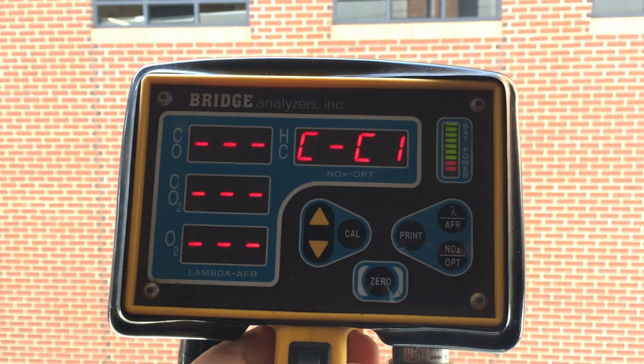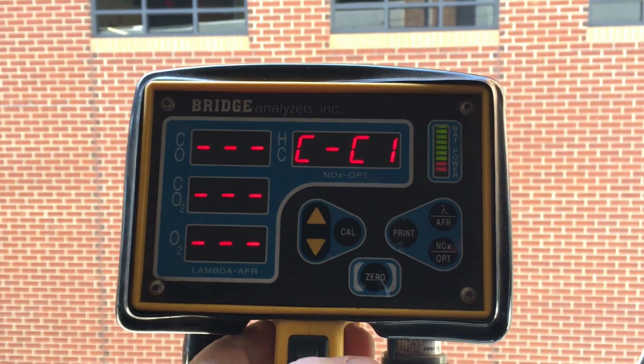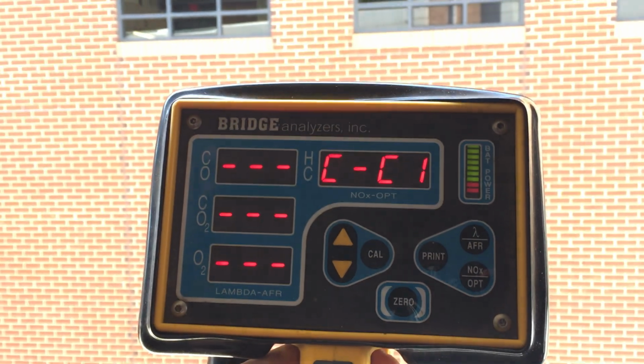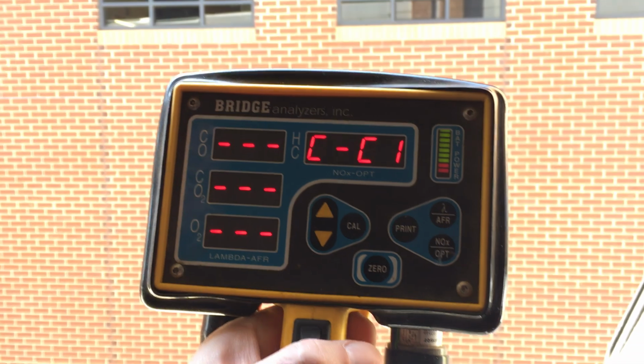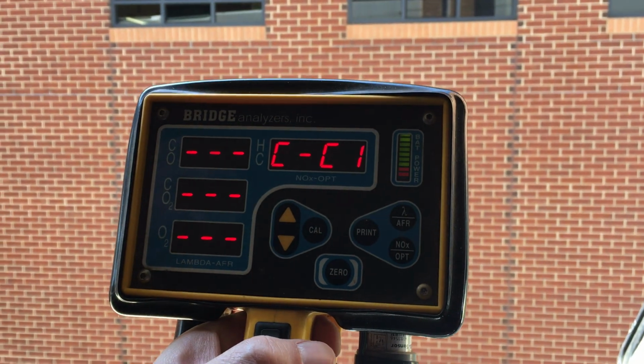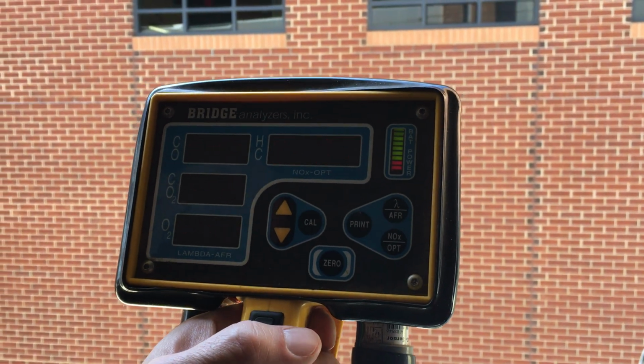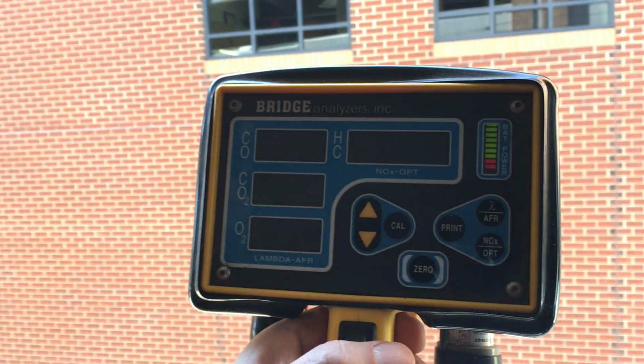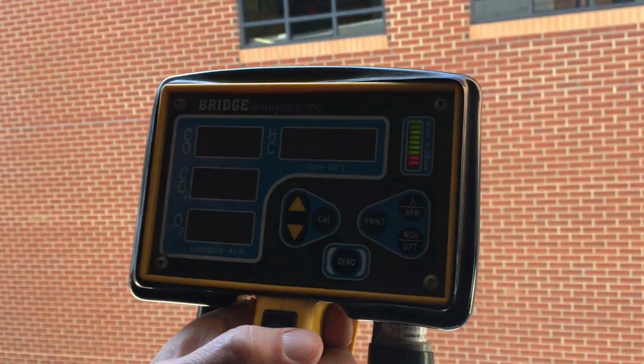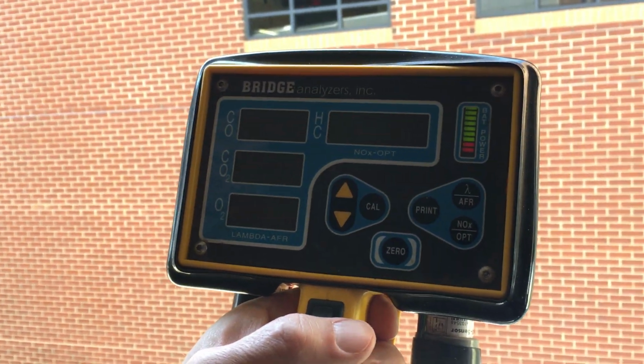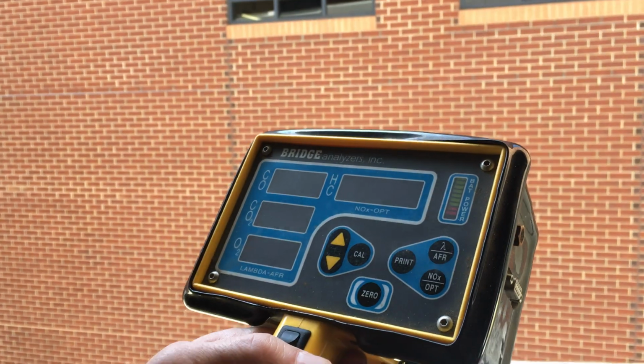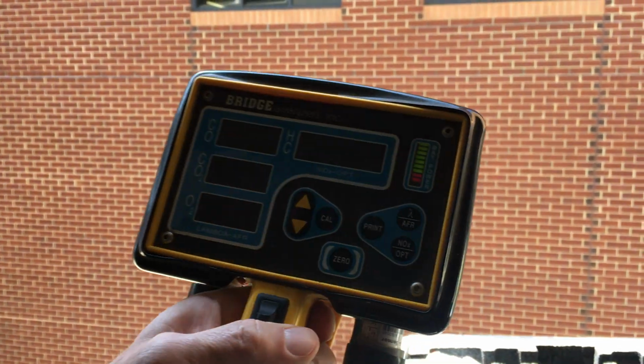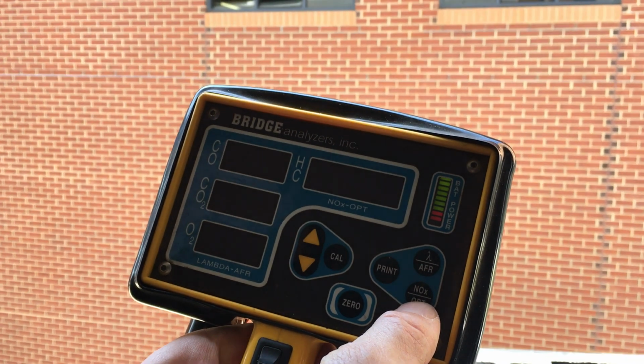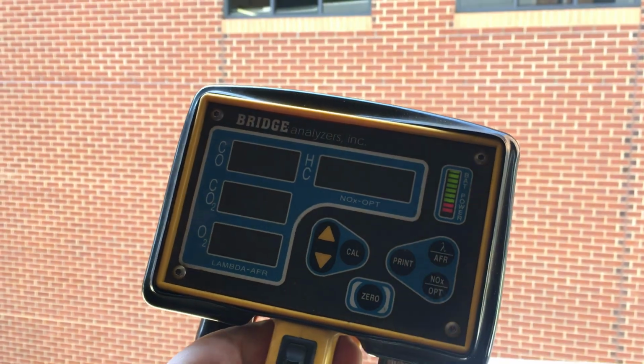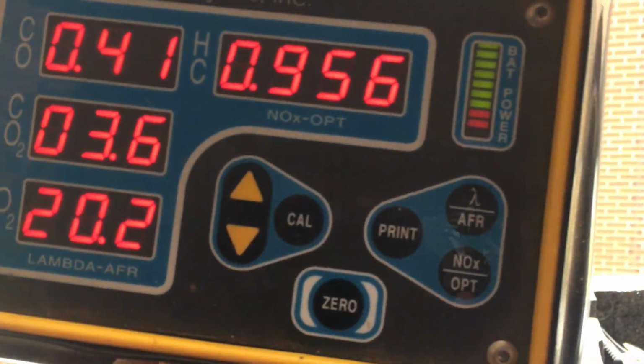All of the sensors on this are carbon monoxide, carbon dioxide, oxygen, and hydrocarbon, and this is a 5 gas. We can also do NOx, and NOx is displayed on the hydrocarbon setting as well. It options off, and I believe we're just going to hit the NOx option and it will toggle back and forth between NOx and hydrocarbon.